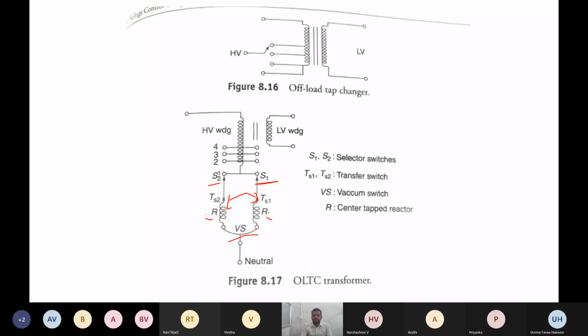So the load current, here we need to consider the load current, and this load current should not be interrupted during a tap changing only. So at that time what happens, if you are placing a tap from position 1 to position 2, at that time you can witness some voltage differences. That voltage difference we can witness at the time of changing the position of some taps. So here we are using different tap selection switches and reactors.